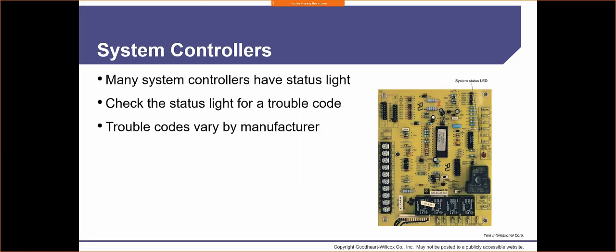We also have system controllers that are going to help us make adjustments and tests. These are really nice because they have a little LED light. This board has one right here, and this one's going to give you a little status light or a trouble code. So basically what's going to happen is that light is either going to stay on the entire time or it's going to blink. And depending on how many flashes you get, that's going to indicate what type of problem we have. Or there is no problem. Maybe it's just running like it's supposed to.